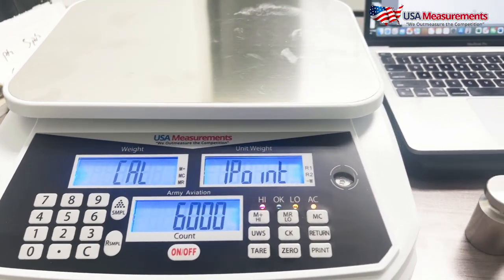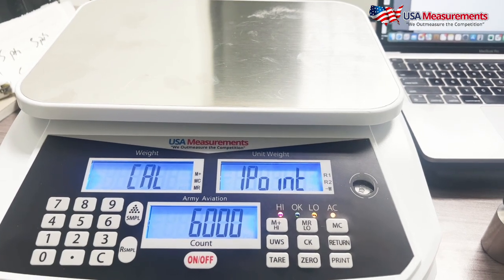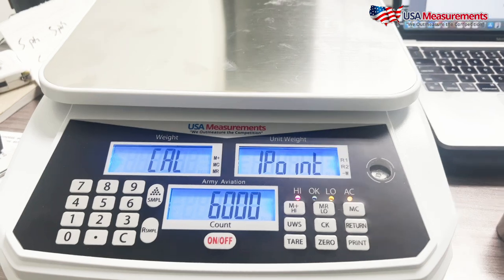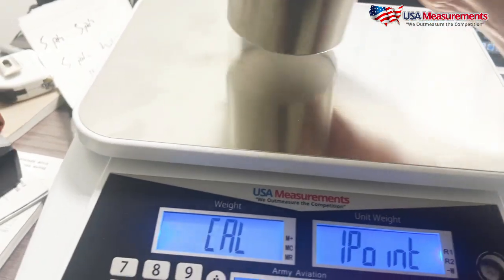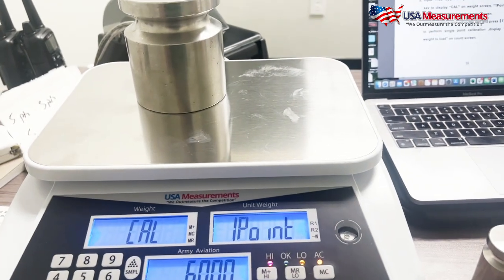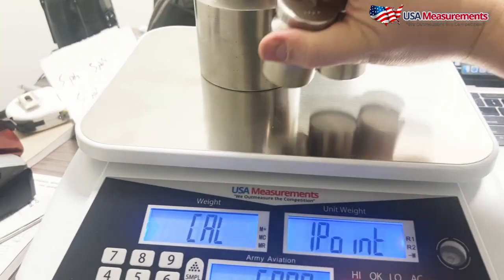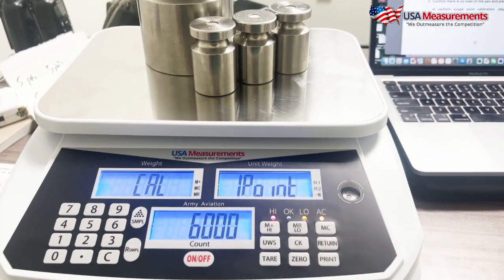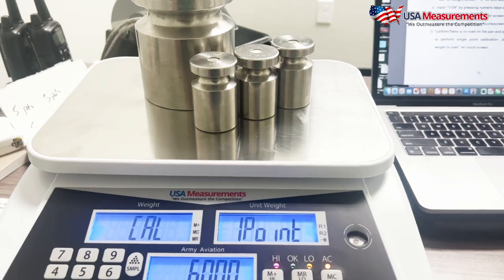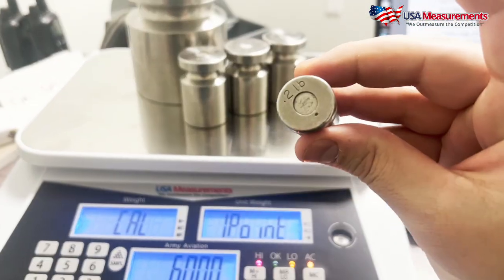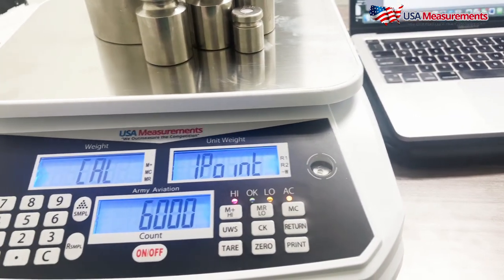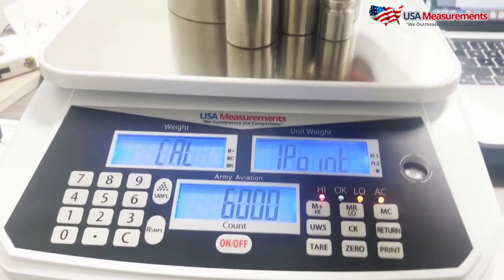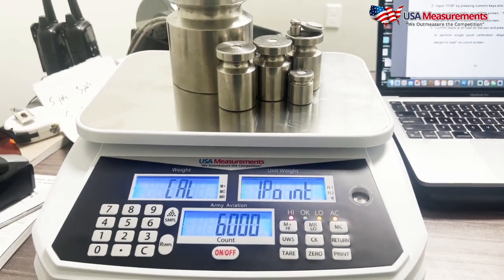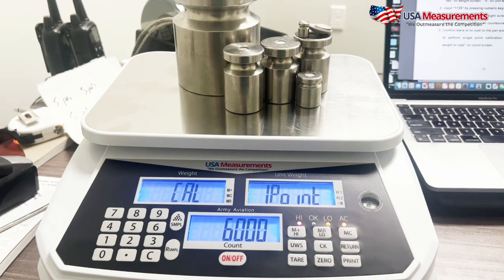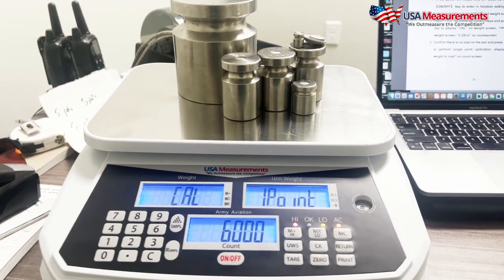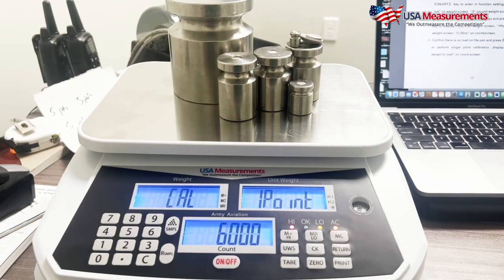So 6,000 grams will be the equivalent of 13.22772 pounds. So to calibrate this scale, I'm going to be using a 10-pound weight along with three 1-pound weights, giving me a total of 13 pounds. And then 0.22772. I happen to have a 0.2 pound weight. I also have smaller weights here that I'm going to be applying as well to get as close to the decimal place as possible. Now, if you don't have these types of weights, I do suggest contacting your local scale service provider to come calibrate your scale for accuracy.